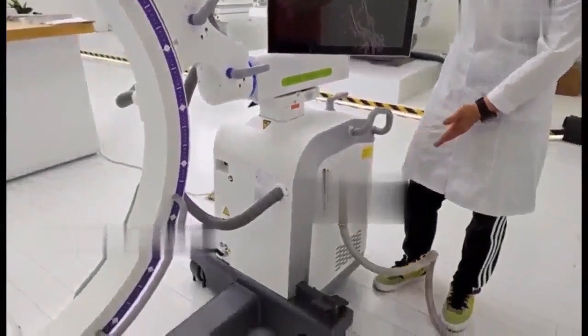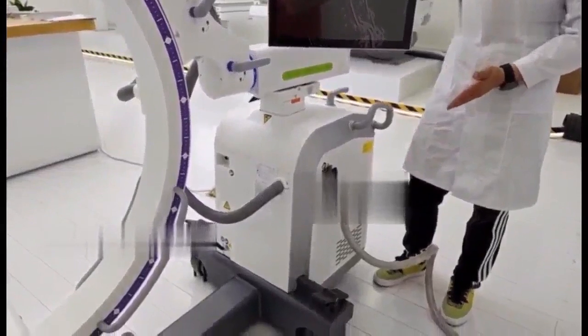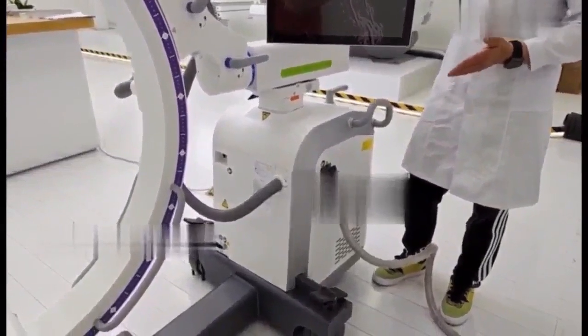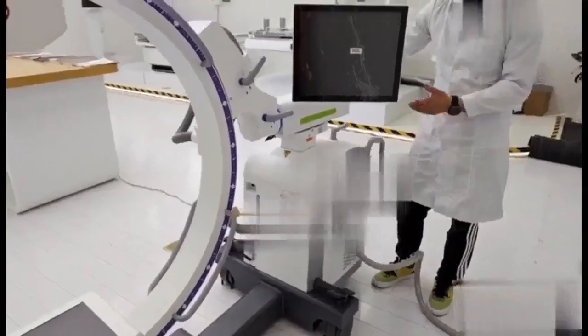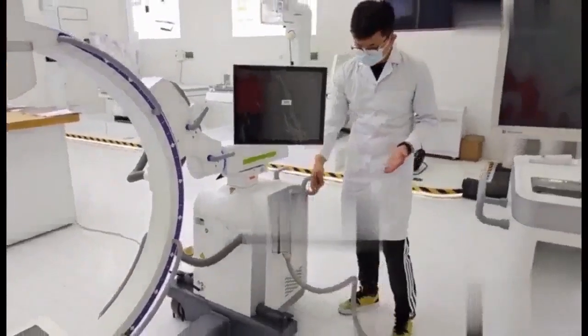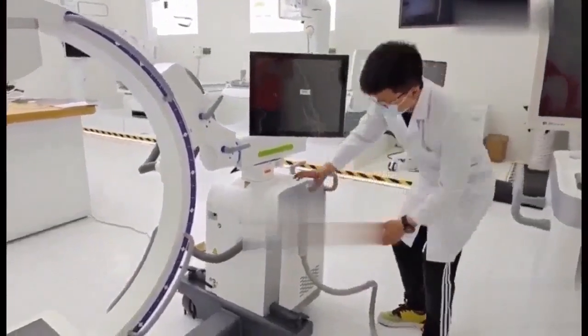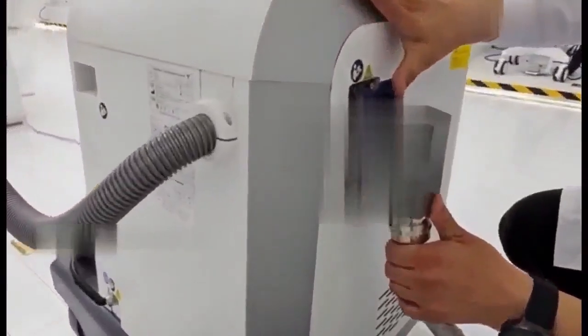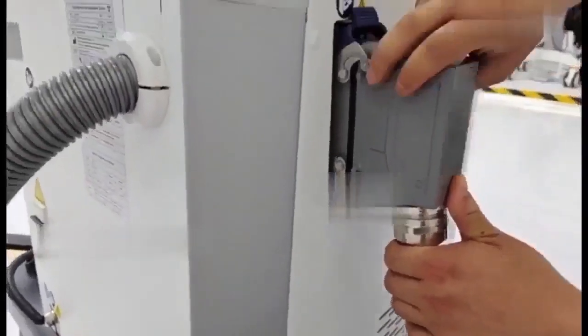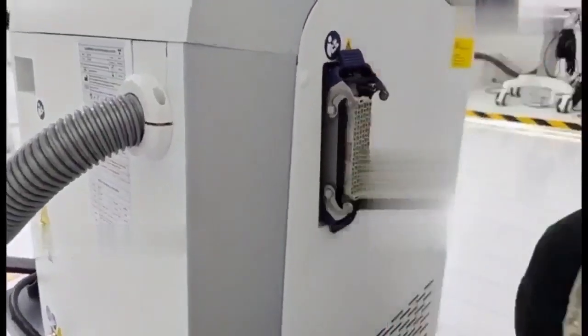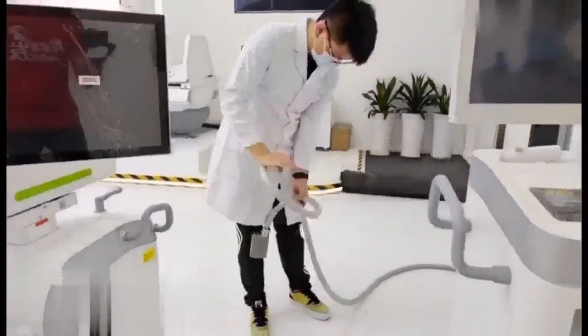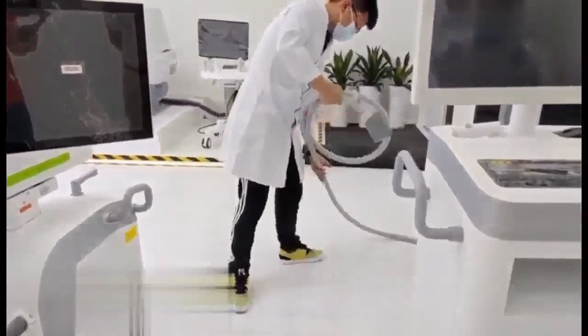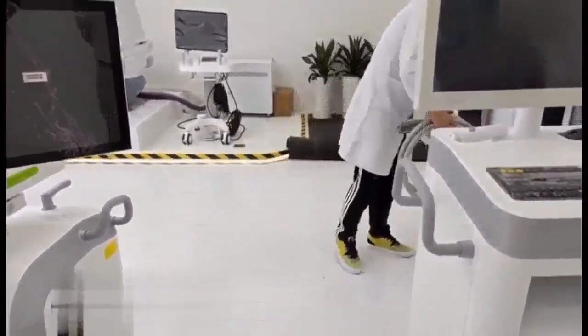This is the heavy-duty connector. If the C-arm is used in one operation room only, this can be left connected. If it needs to be used in different operation rooms, this needs to be removed. Unbuckle the upper side of the blue buckle, then unbuckle the lower buckle. Directly plug it out and put away the heavy connector, in a similar way to how you put away the power cable of the main unit.